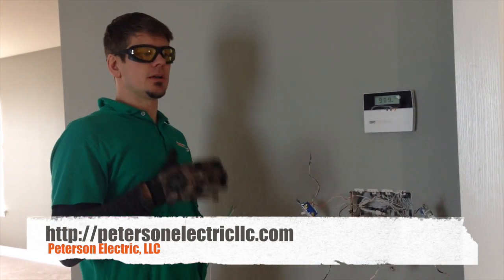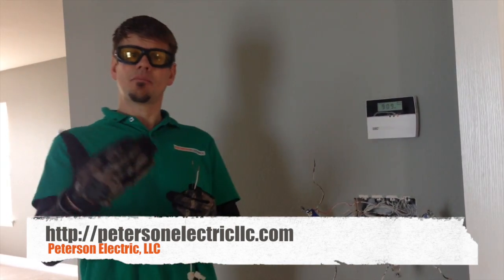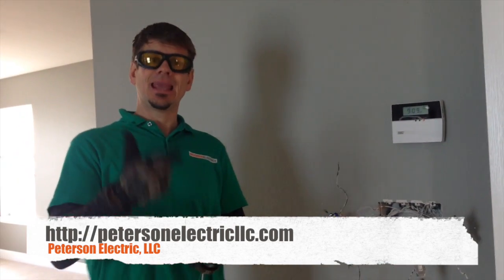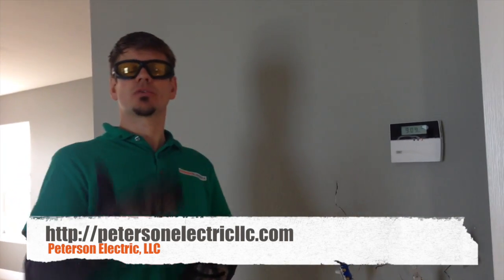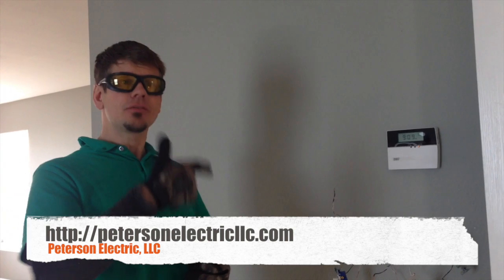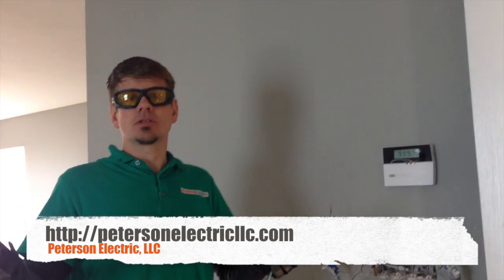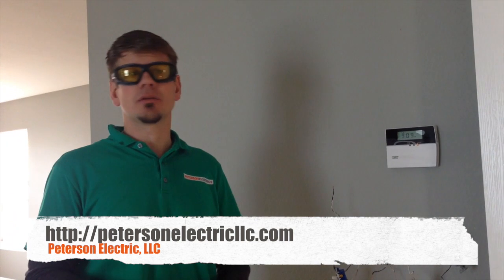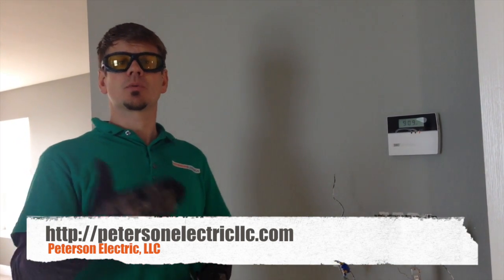Now I'm at the point where I know that my two phases are tied somewhere. Why does that matter? Well, I'm not able to get the arc fault to set on the neutral side right now. And I have to get it to set, otherwise the arc fault is no good. I'm charging her $65 on a breaker that could have been put in for about $8, besides the fact that now it's not doing its purpose, which is to protect.